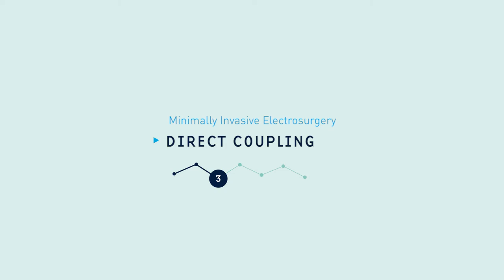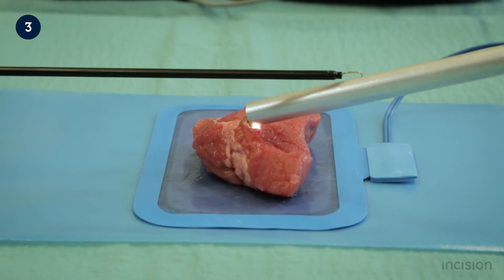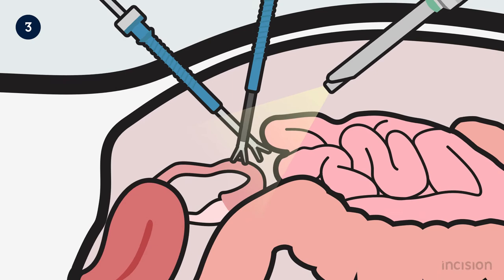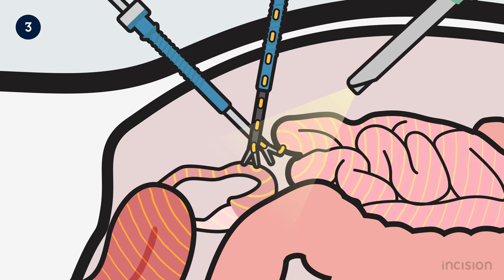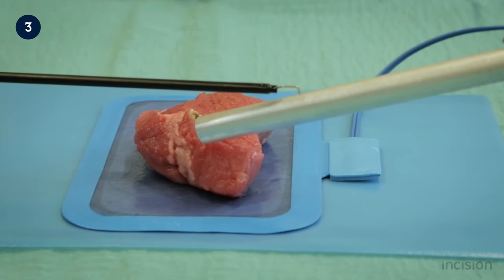Aside from the electrode tip accidentally touching unintended tissues, there is also a risk of the electrode tip touching or being near to other conductive instruments. Upon activation, this can cause alternative conductive pathways to form via unintended tissues, which have a large chance of being negatively affected by the passing current. This is known as direct coupling and can result in the burning or perforation of structures.